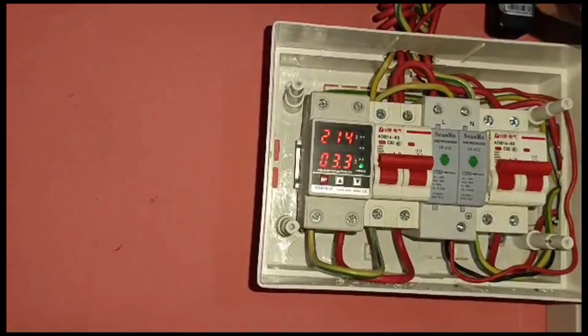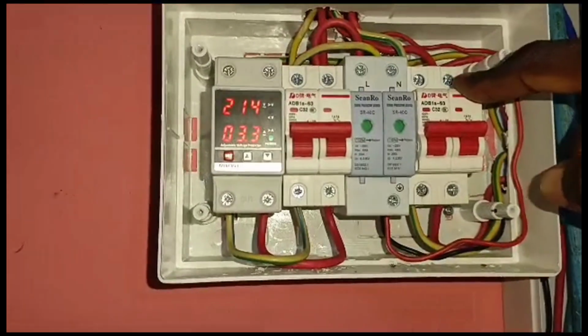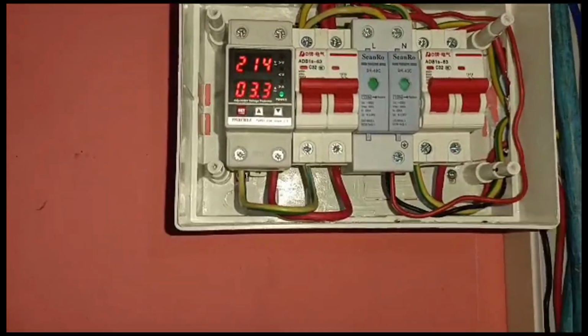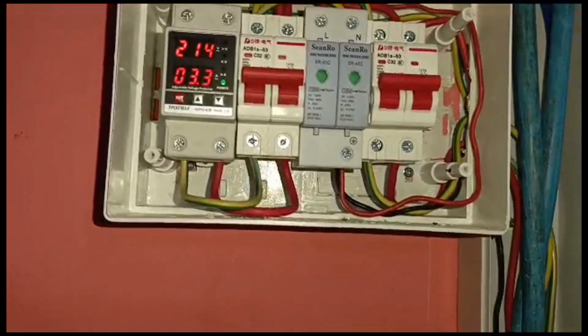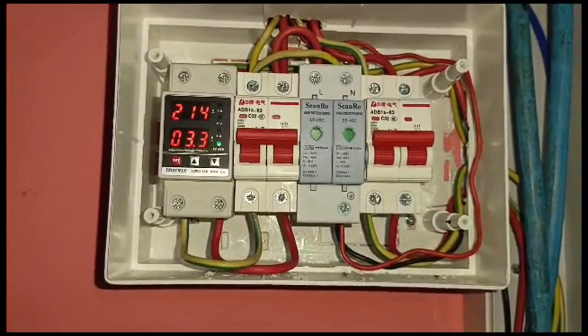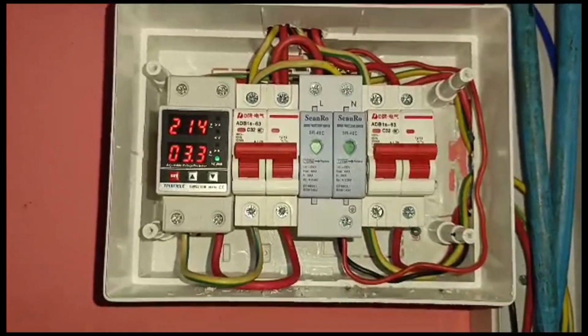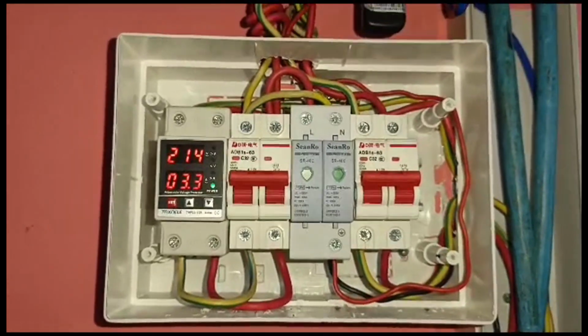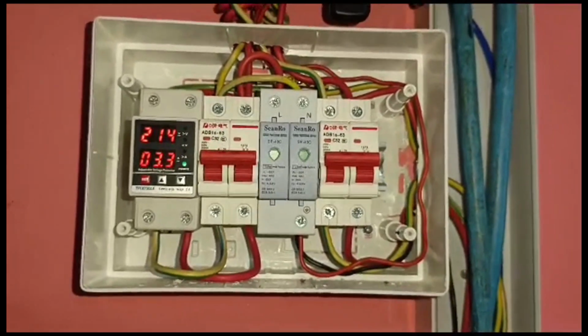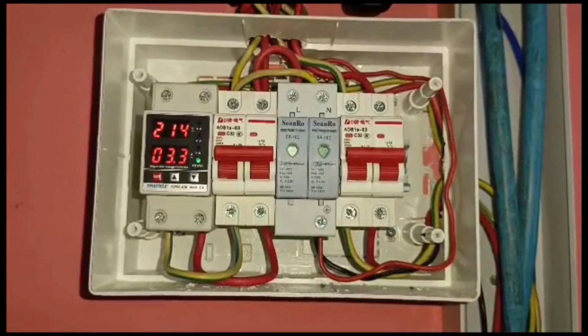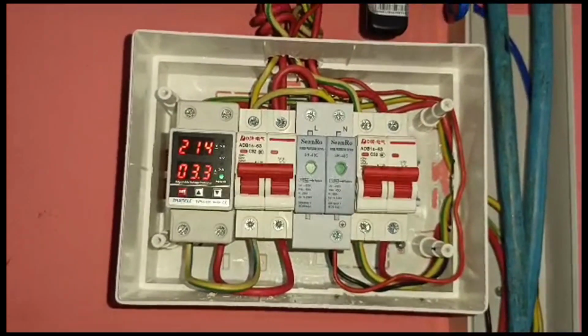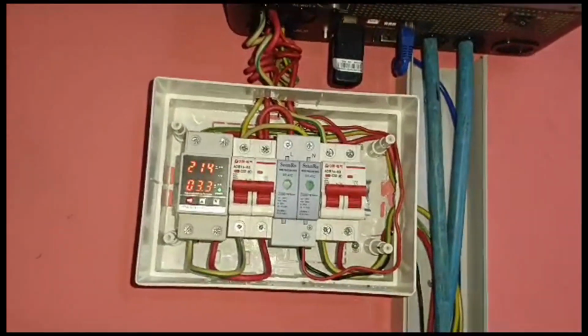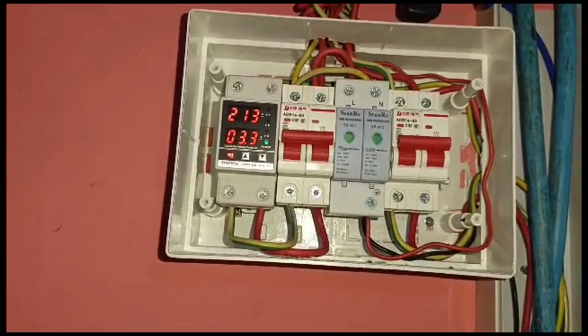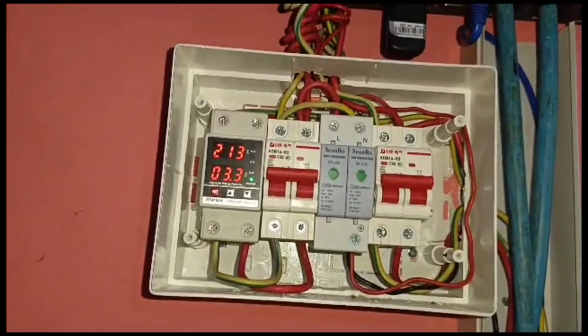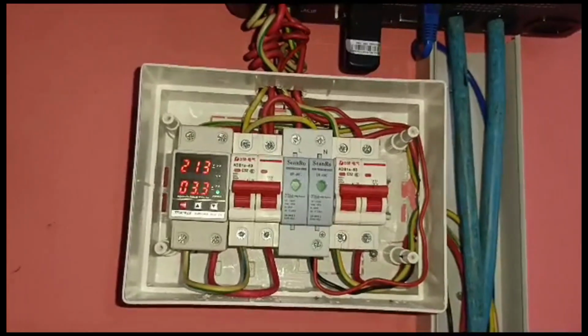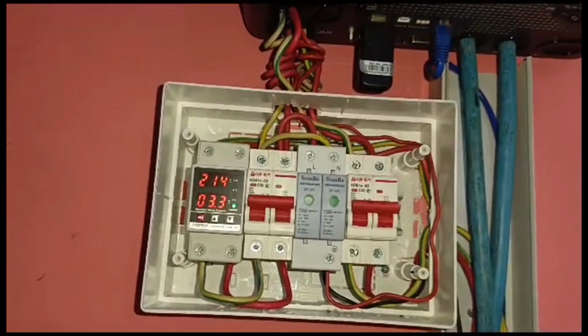So it goes into the inverter, and the output of the inverter comes out through this circuit breaker before it goes back through this hole to a knife switch at the other end. What the knife switch does is switch between the grid power and the output of the inverter. If something goes wrong with the inverter, you can quickly bypass the inverter and put the critical load back on the grid, so that you have enough time to fix the problem with the inverter. So that's the AC side.